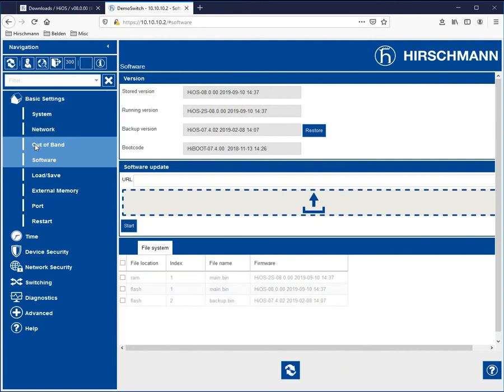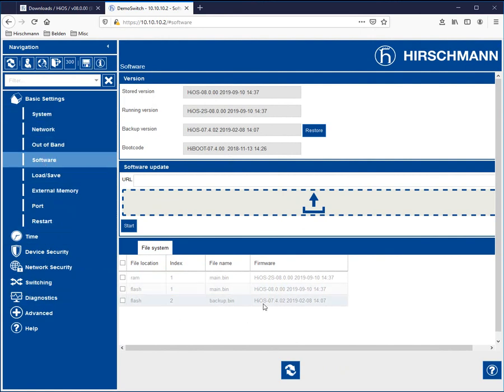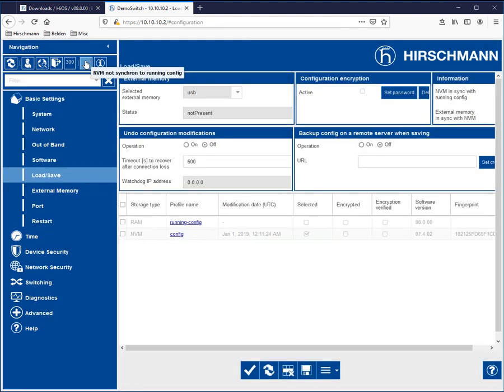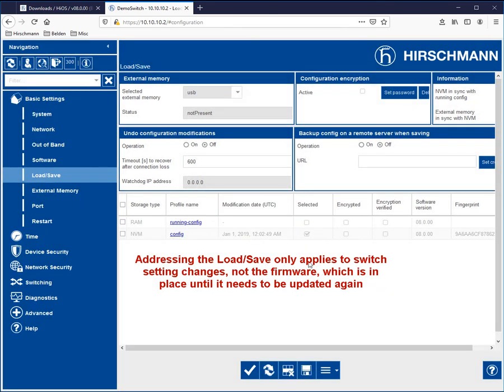The only thing that you do need to keep in mind is whenever you do make any changes within the switch, you always will need to address the fact that any changes that are made are stored in volatile memory. And you will need to go to your load save and click on the save icon down here. This puts any changes into non-volatile memory and this prevents any configuration changes from being lost during a power cycle of the switch.